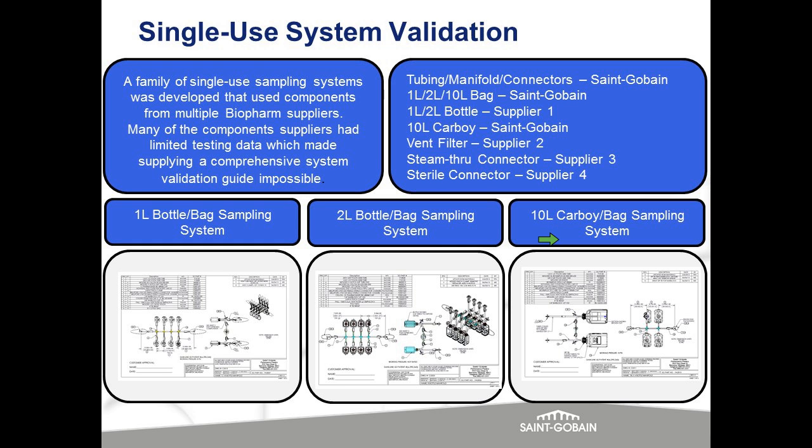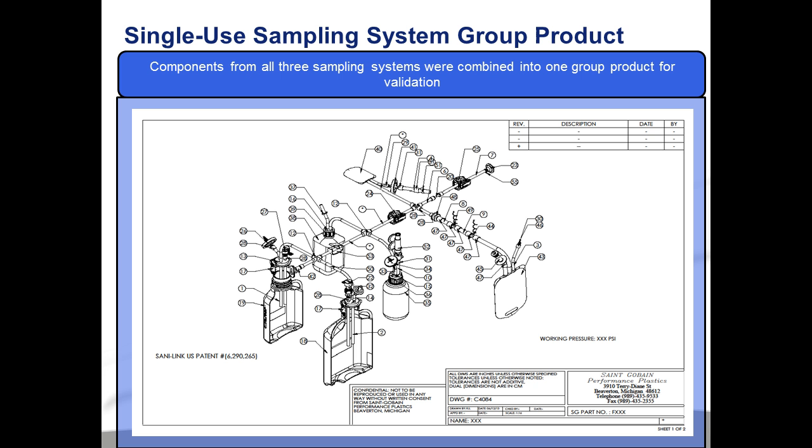So what we've done is we've started putting together monster systems where we'll take a family of products and then do full validation testing, including E&L, where we can either do a composite test at a higher surface area to volume ratio, or we can do more in-process leachable tests where we do the actual conditions.